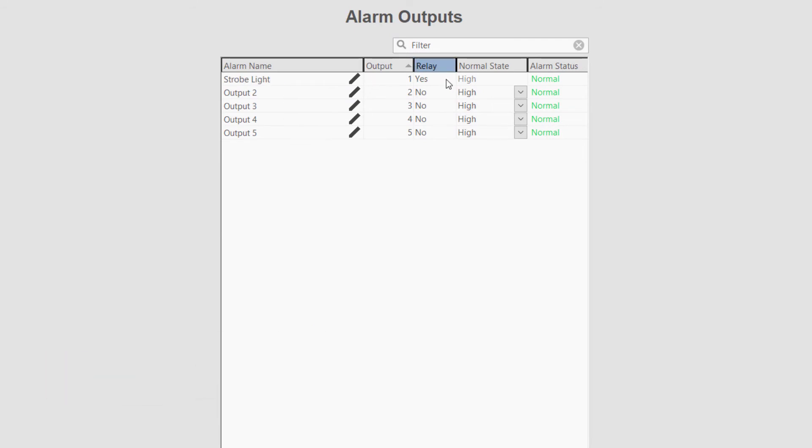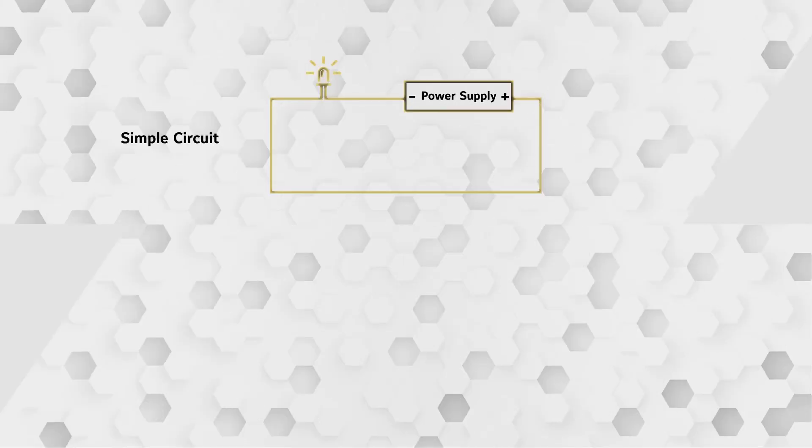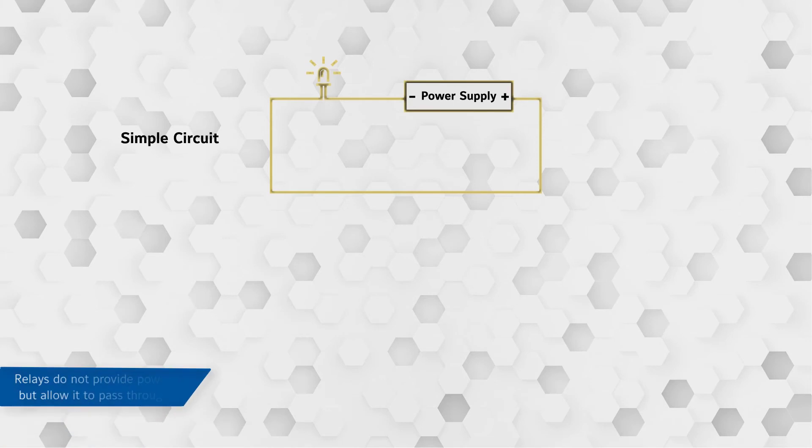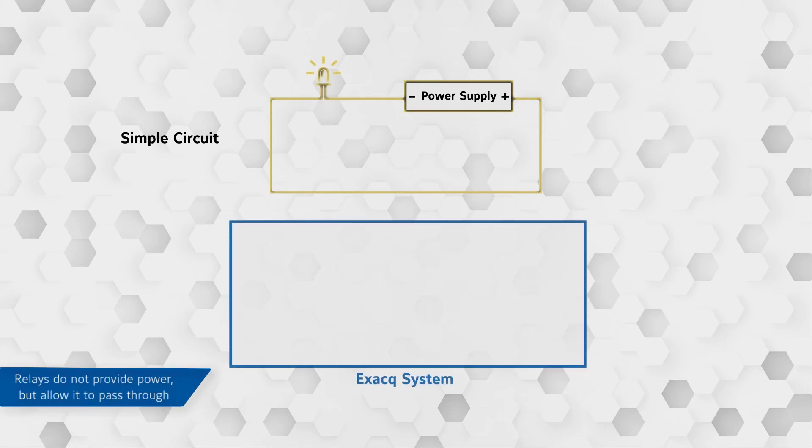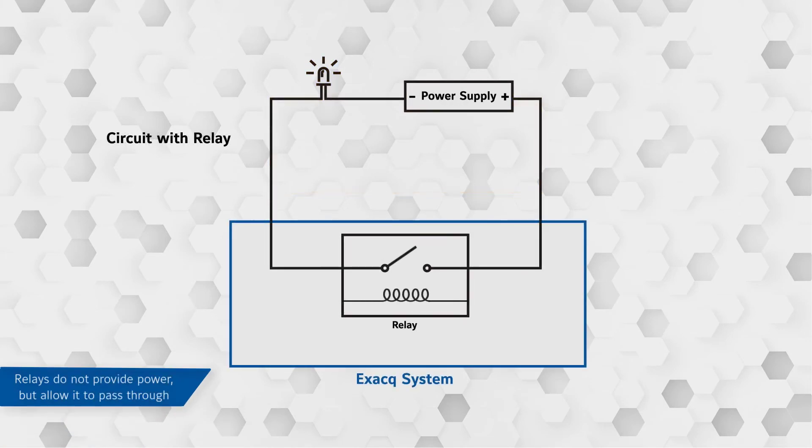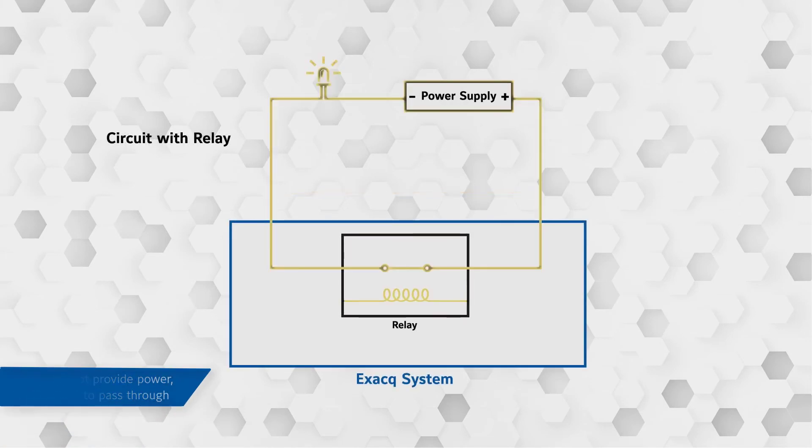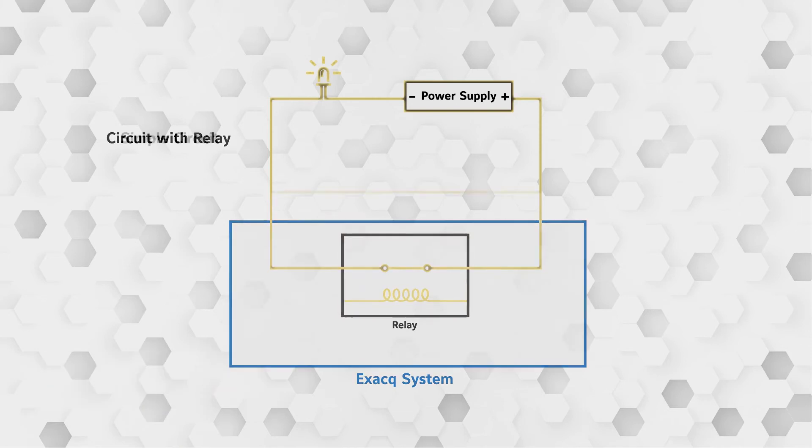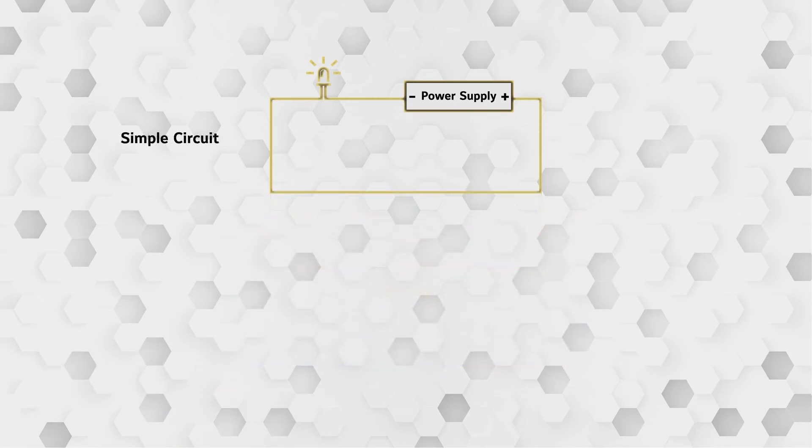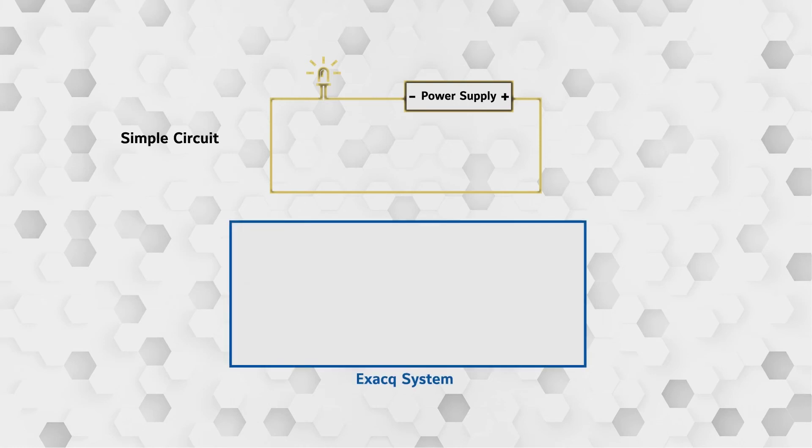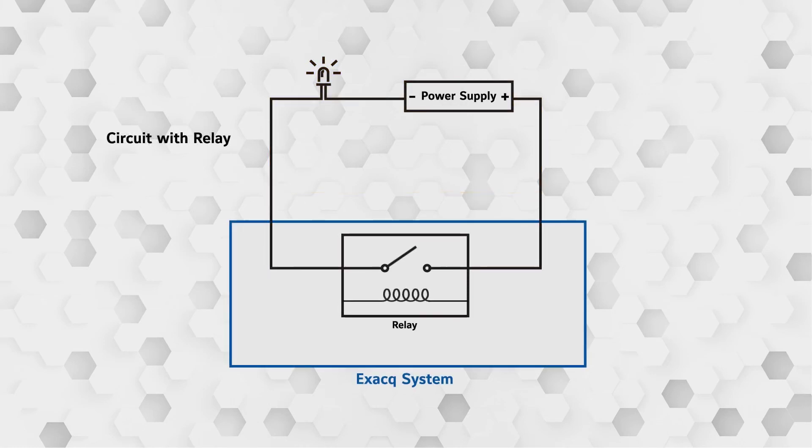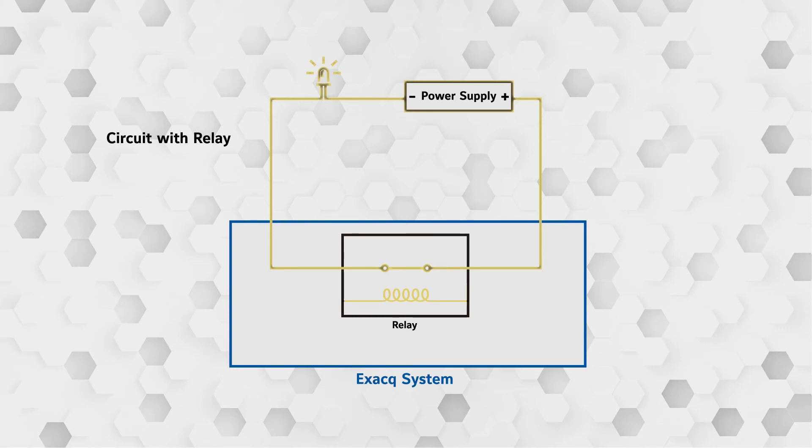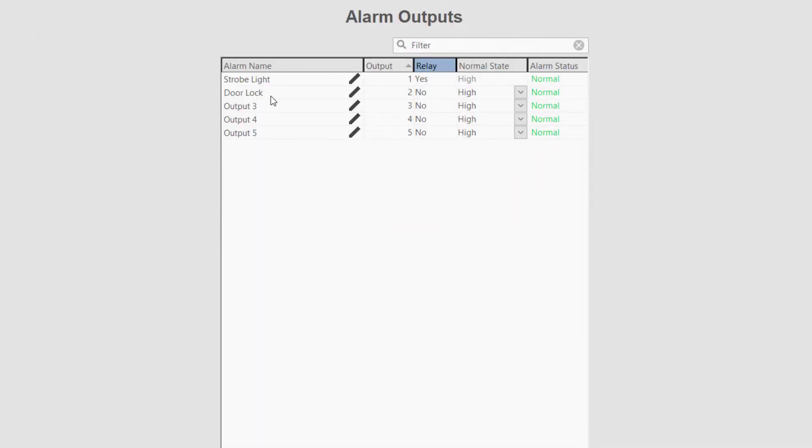The Relay column will indicate if the alarm output is a relay or not. A relay is an unpowered switch that merely breaks a point in the circuit and closes it when activated. This means that the current connected to it must be powered. When in an alarm state, the relay closes and completes the circuit, passing the current to the device connected. The maximum power applied should not exceed 24 volts DC and 1 amp max.